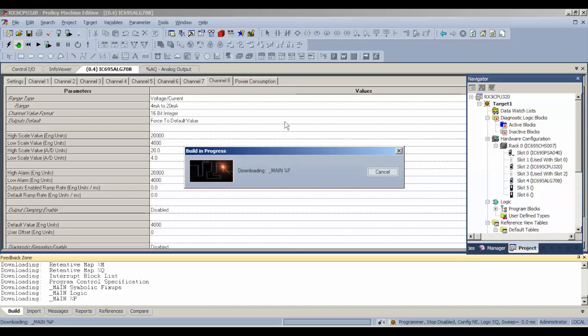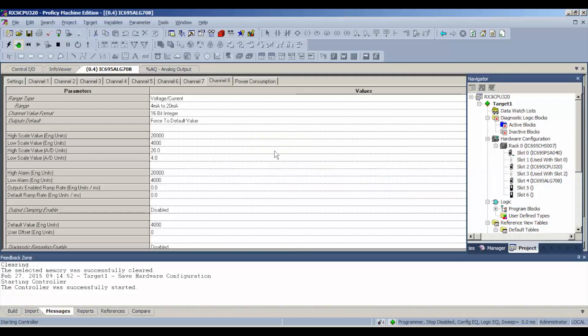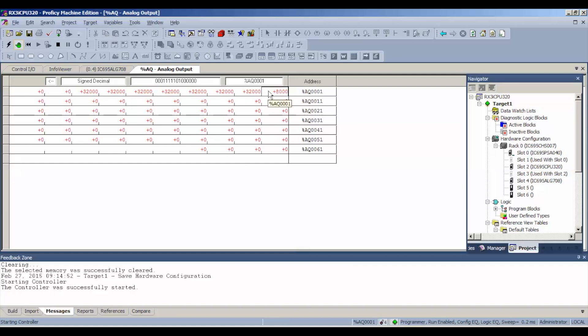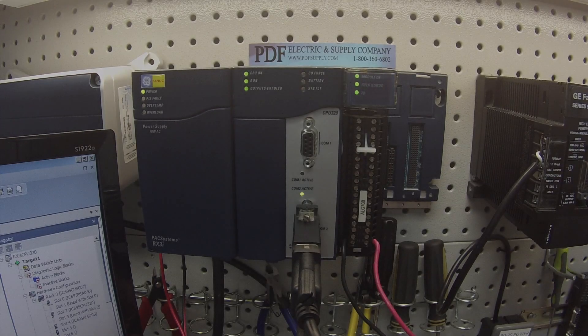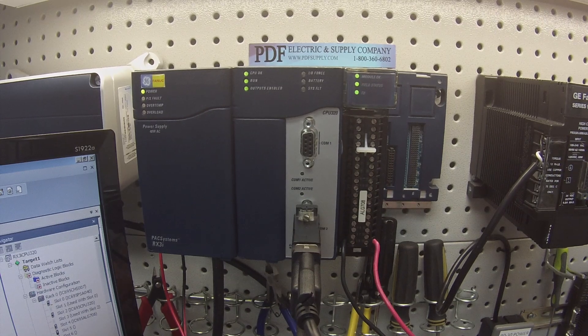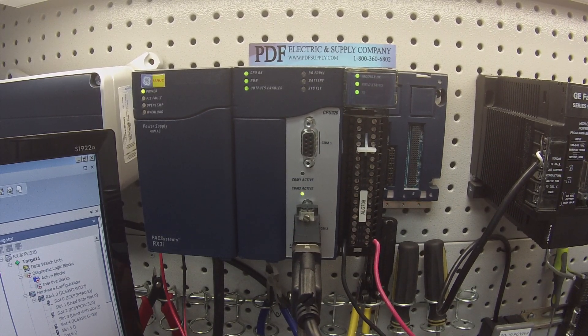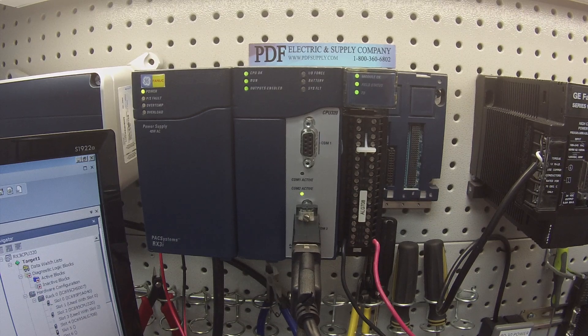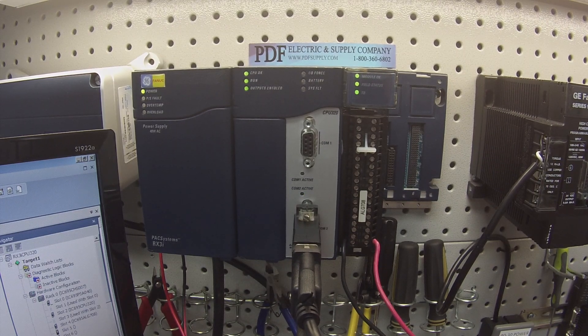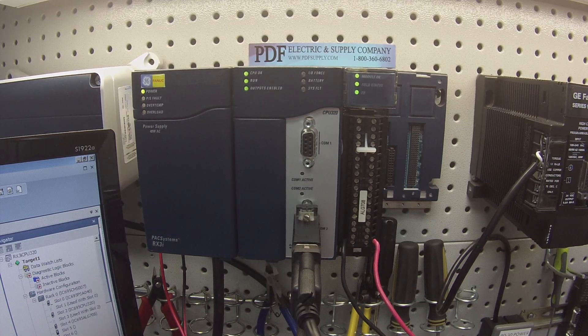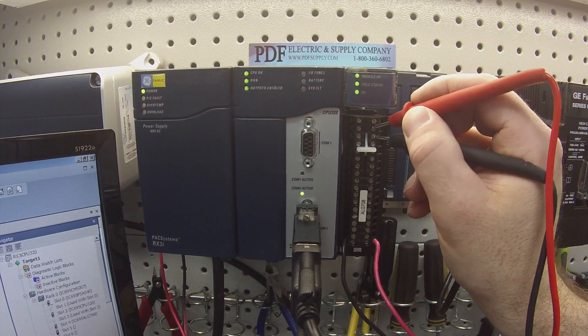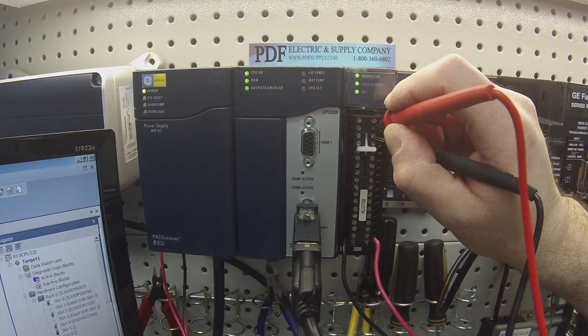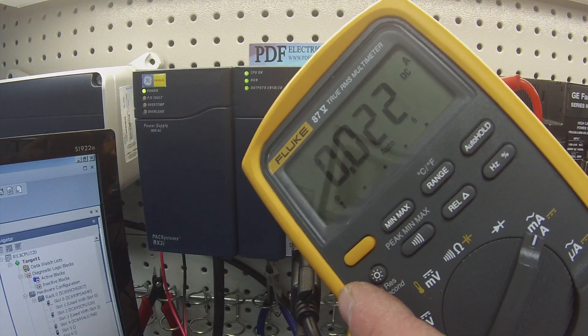Now, you want to go about this the same exact way that we went about the voltage, meaning that you want to try different values. It's good to see that it can go to full value, but it's also good to see the value cut in half. We still have our values here. I'm going to bring channel one back up to 32,000. I'm going to touch my probes now. Here's where you want to keep in mind that we're touching different terminals for these readings now, not the same terminals. Milliamp is measured. Channel one, for example, is measured on 20 is where your positive lead goes and 21 is where your negative lead goes. This is perfect. My reading is 21.